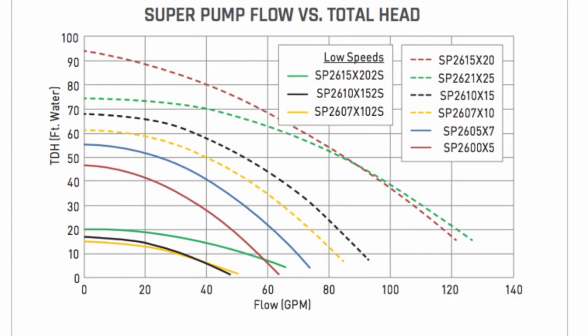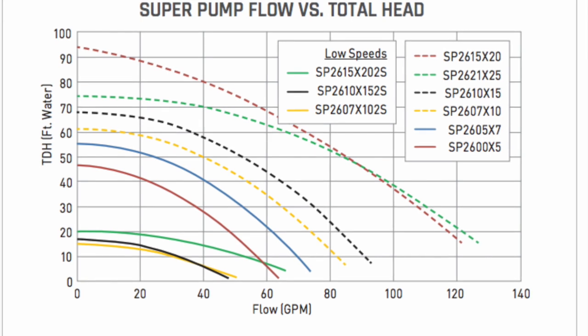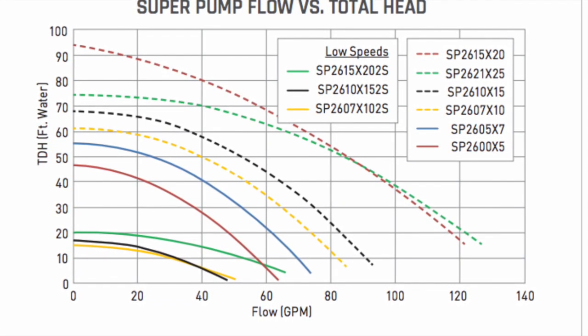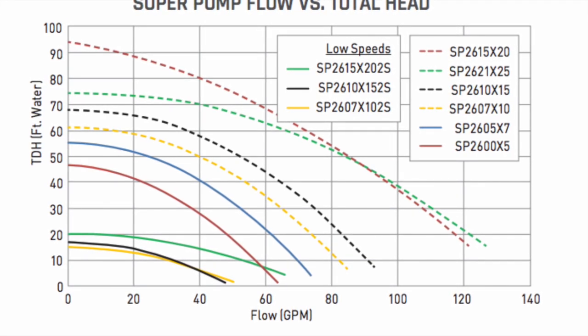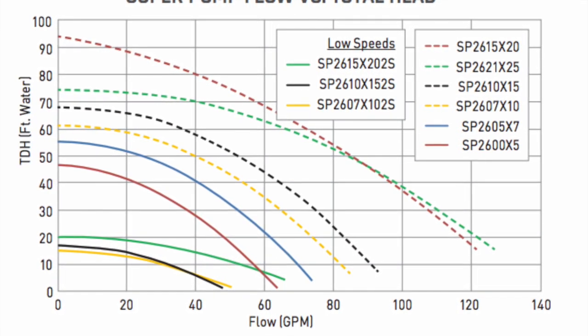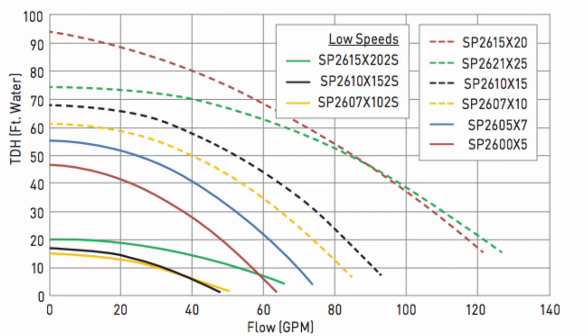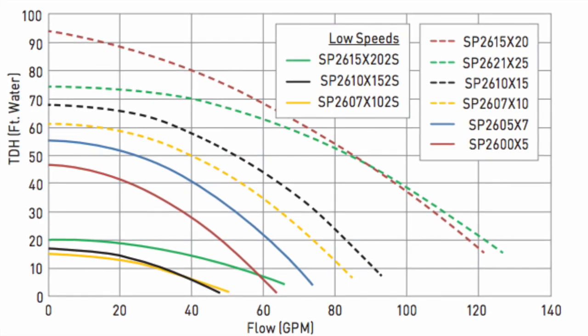This is where the benefits of a variable speed pump come in. You can get a three-quarter horse pump, a half horse pump, or a one horse pump — they all have an impeller and a pump curve. A pump curve is essentially a performance chart that outlines the performance of the pump based on the load, or total dynamic head resistance it has to push against, and that dictates the gallons per minute the pump can push. The more total dynamic head, the fewer gallons per minute the pump can push.